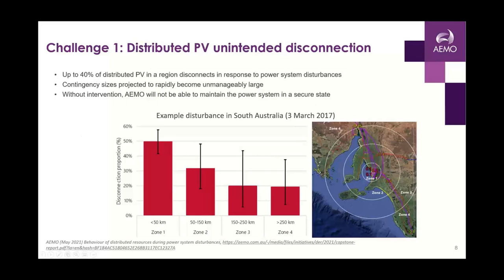Just a bit more background, we have actually seen events where a lot of distributed PV disconnects in a region. Once again, this is in South Australia. Following a system disturbance, we have seen up to 40% of distributed PV in a region disconnect. You can see that as we go out from the location of the event, it does reduce, but we do see quite large amounts of distributed PV disconnect close to the event.